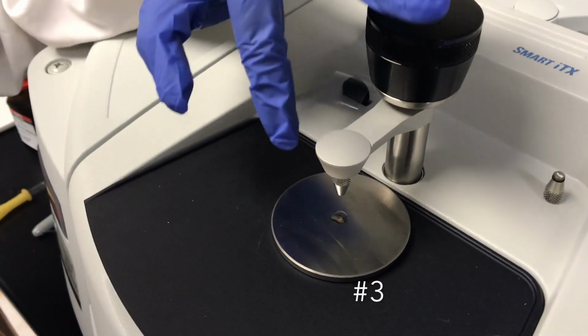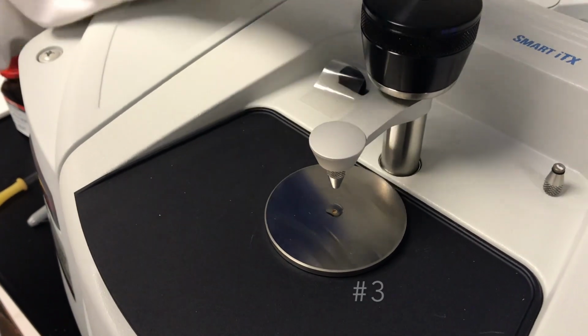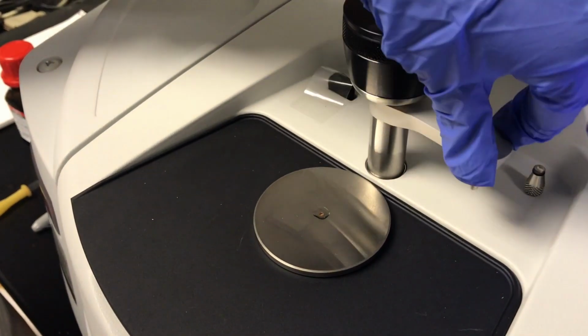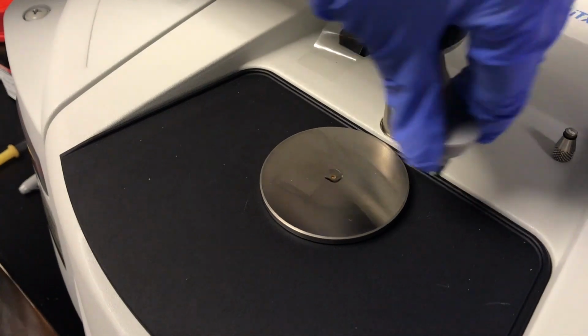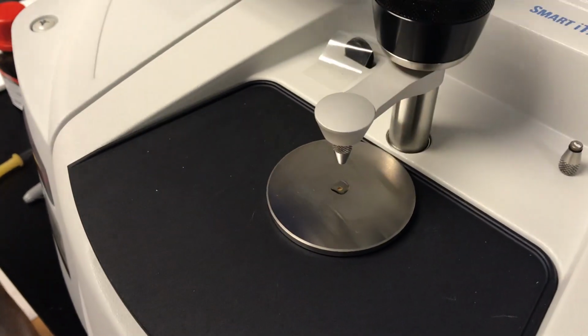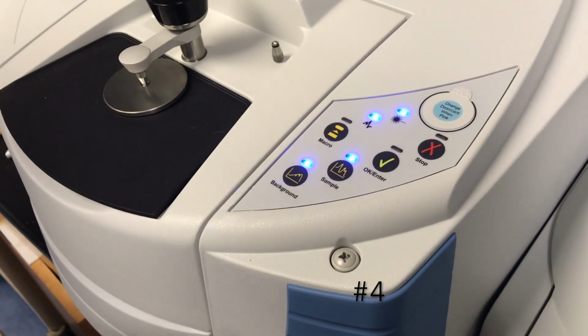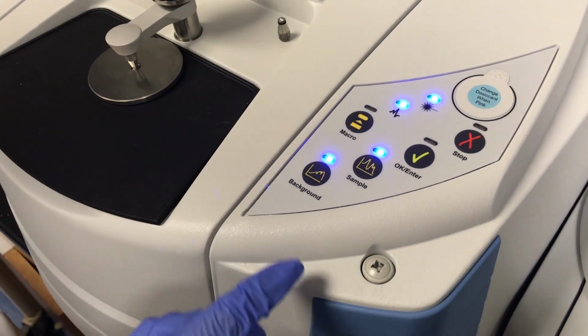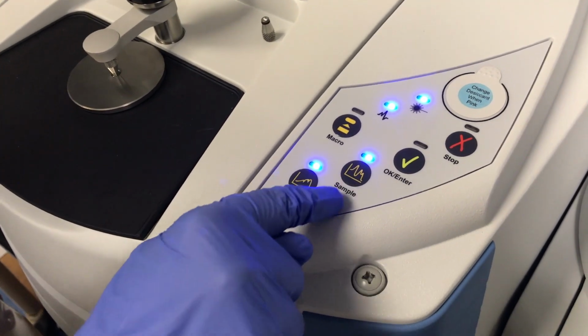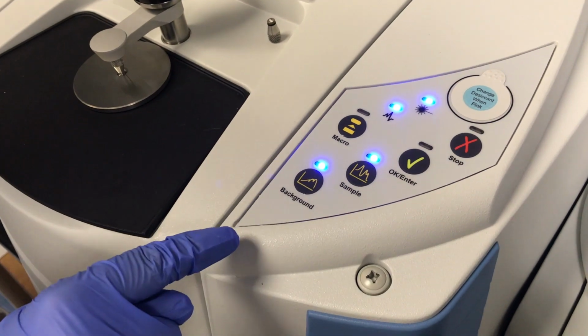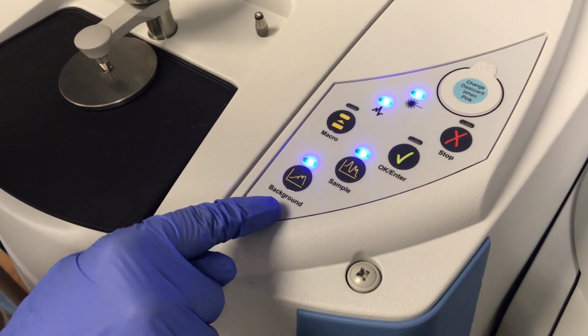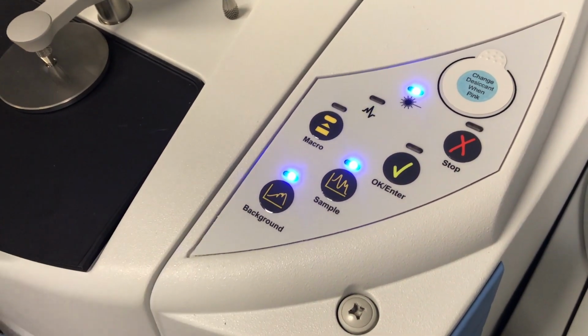If this gets in the way while you're loading the sample for a liquid or solid, you can always turn this out of the way, and then you can just turn it right back once you're ready to analyze the sample. If you don't want to use the computer to analyze the sample, you can just press this button, sample, and then before that, obviously you need to take the background, and here's the background button.